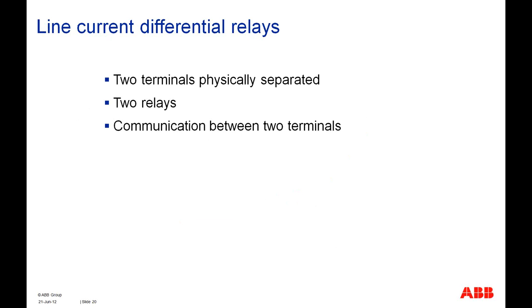But in the case of that was the line, that was the differential protection which we were talking about. But in case of line differential protection, because the two relays are physically separated by several, or in some cases hundreds of kilometers, we have to have a communication link between these two boxes, 2 or 3 or 4 boxes or 5 boxes in line current differential schemes. And we have to exchange the data measured locally and measured remotely to come to some tripping conclusions.